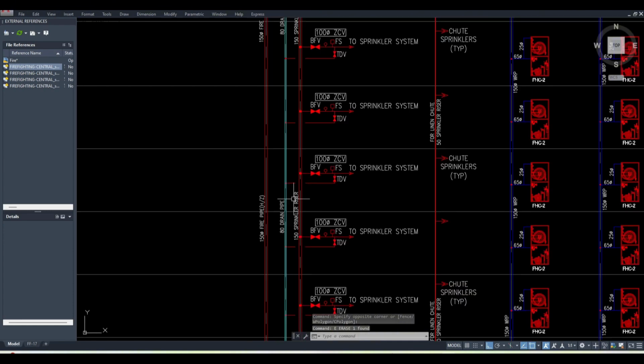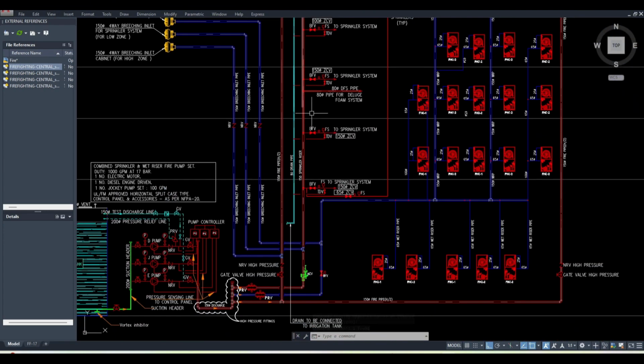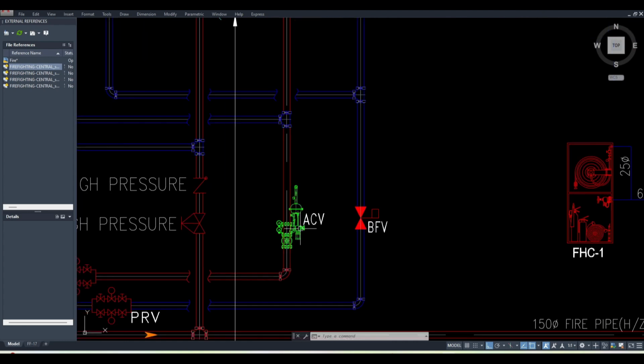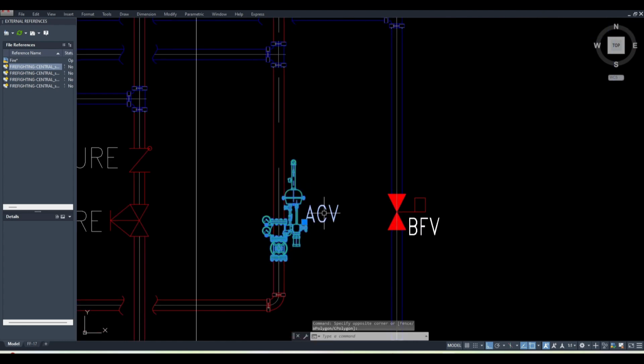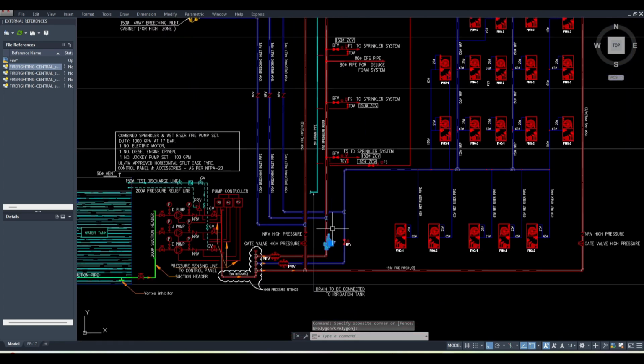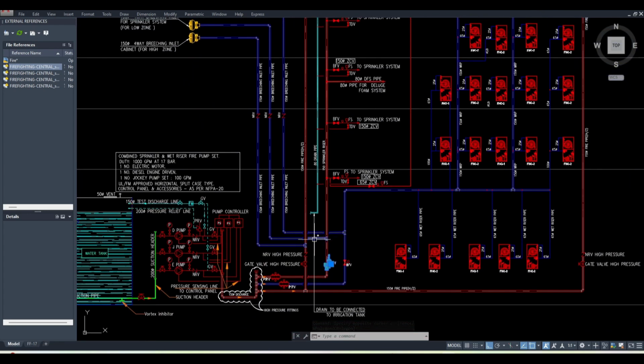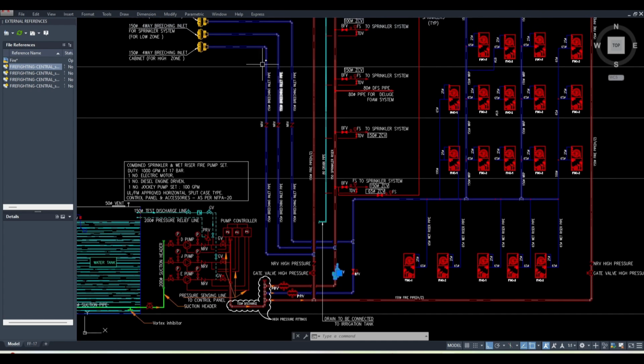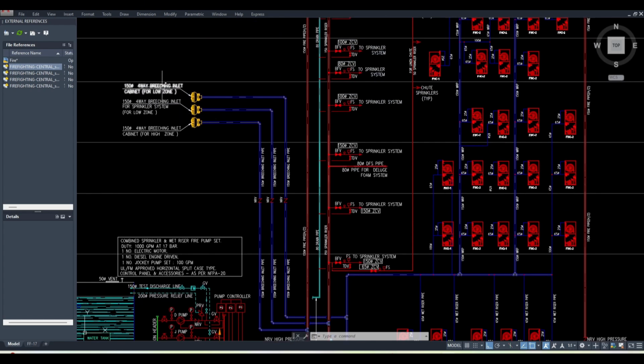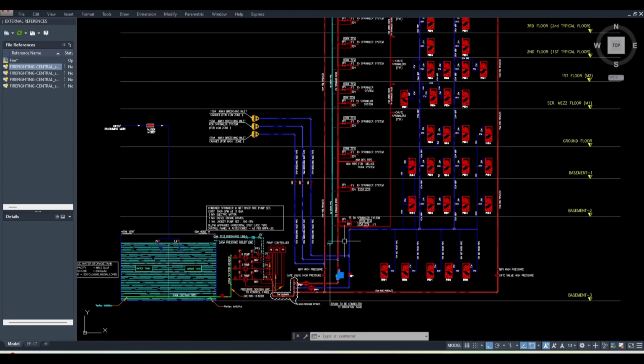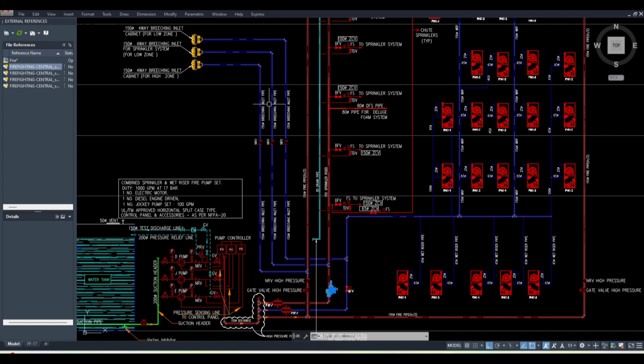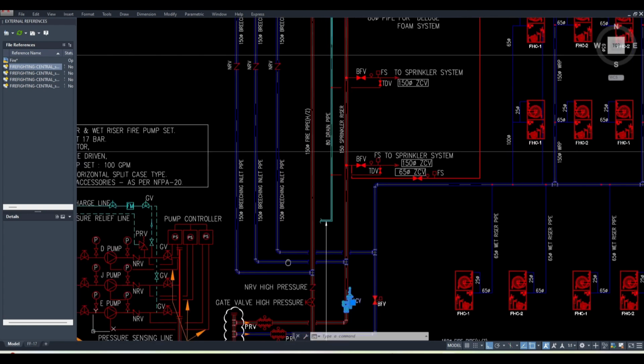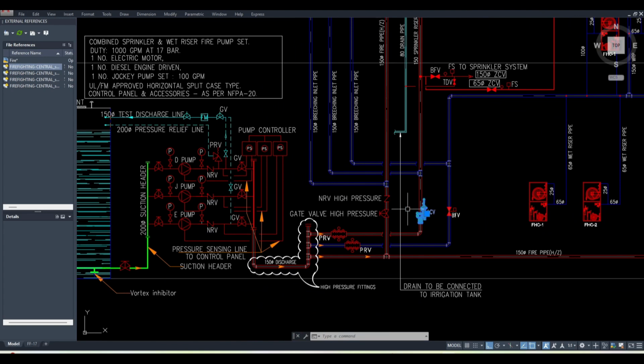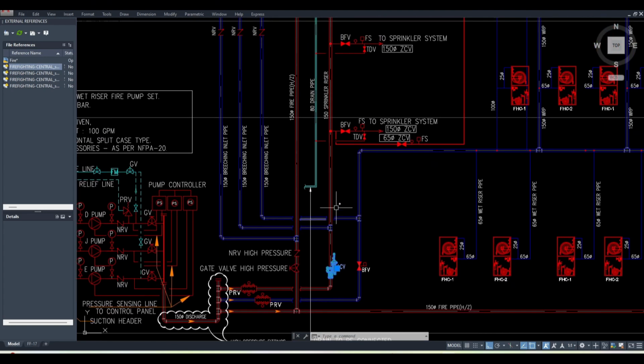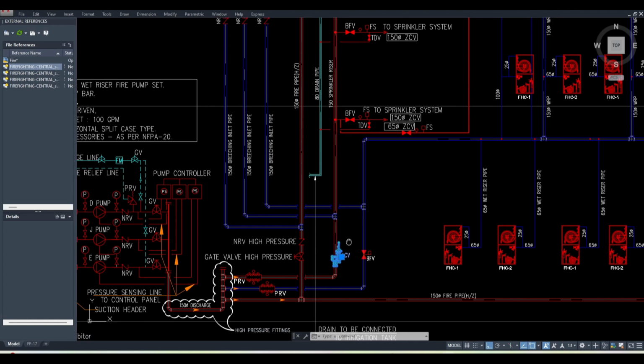Then you come like this, and at the bottom of the riser, an alarm check valve must be there. Now, one more thing you need to care about here. In this line also there is one breeching inlet. You remember yesterday I told you about the breeching inlet, which is connected from the truck coming from the municipality, the fire department, so they can connect. Same as the wet riser system, here also we give one connection to the system directly from the truck, so that in case of failure of this system, they can directly supply water to the system from the truck. So it's like a backup system.